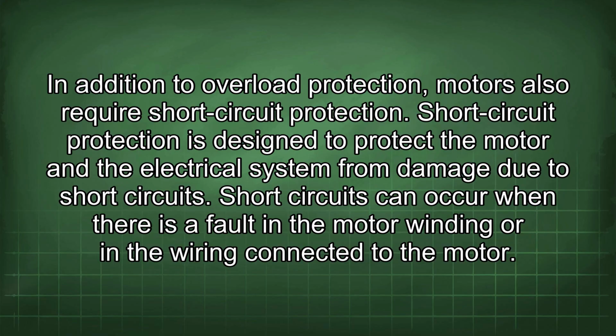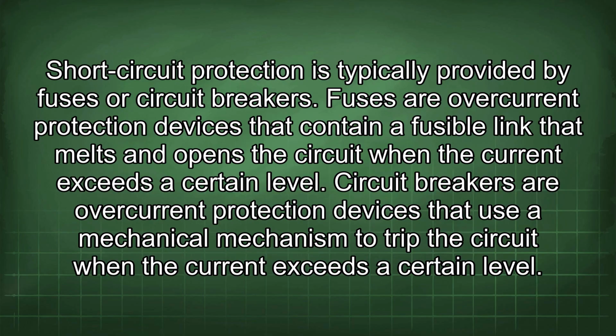Short-circuit protection is designed to protect the motor and the electrical system from damage due to short circuits. Short circuits can occur when there is a fault in the motor winding or in the wiring connected to the motor. Short-circuit protection is typically provided by fuses or circuit breakers. Fuses are overcurrent protection devices that contain a fusible link that melts and opens the circuit when the current exceeds a certain level. Circuit breakers are overcurrent protection devices that use a mechanical mechanism to trip the circuit when the current exceeds a certain level.